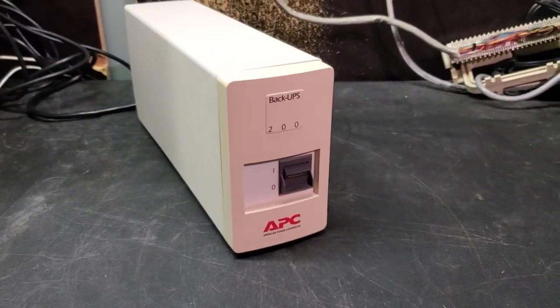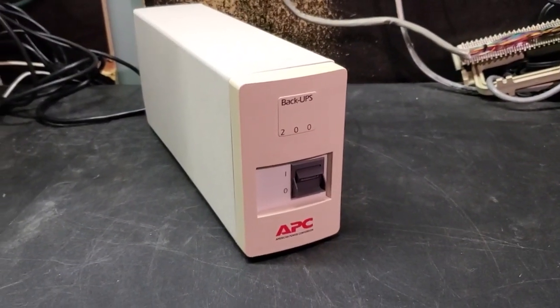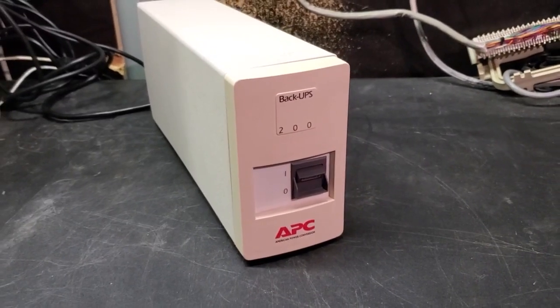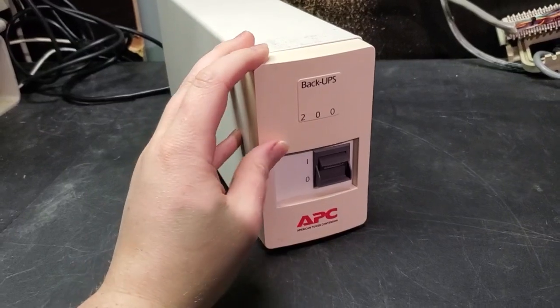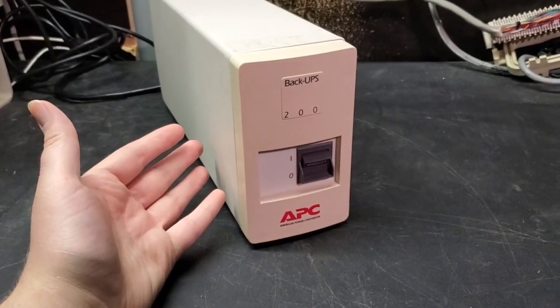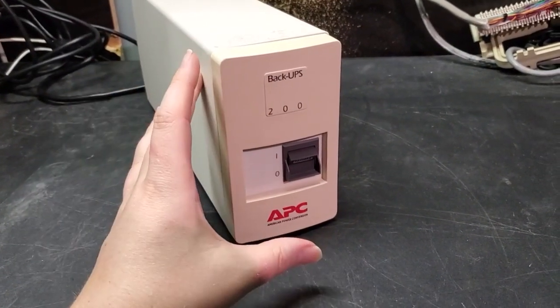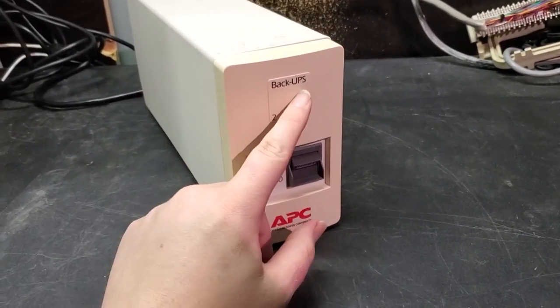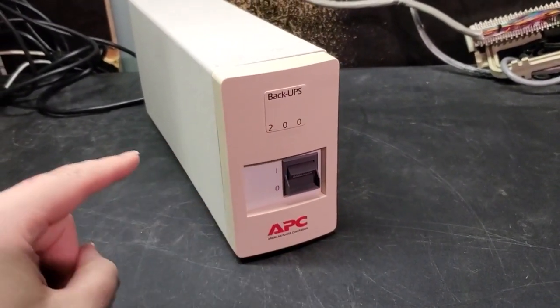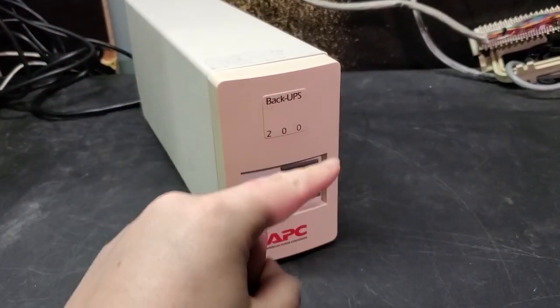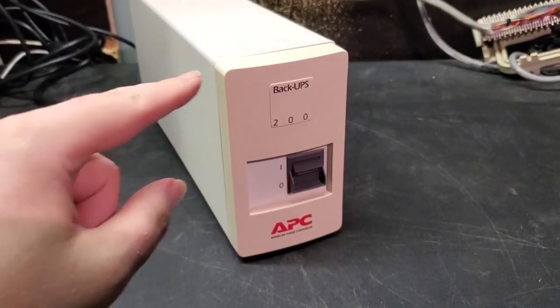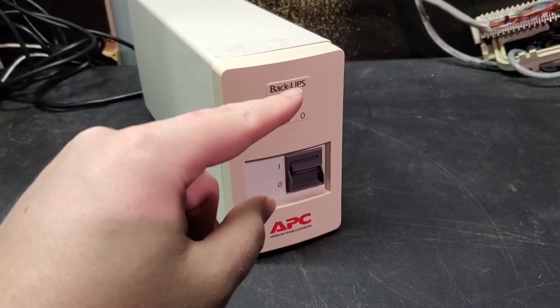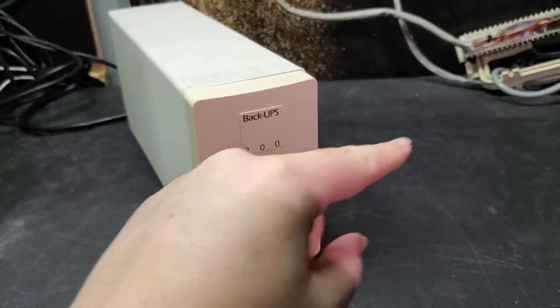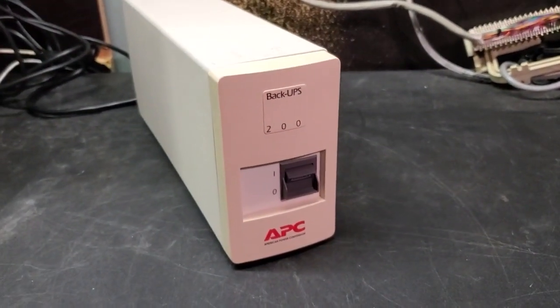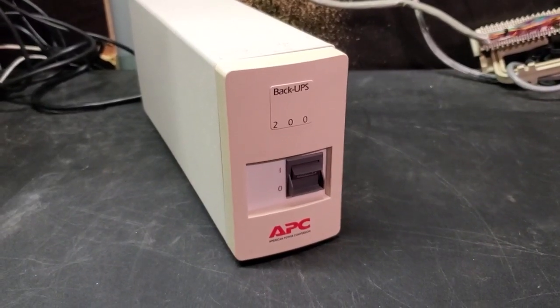Now, one of the implications of this is that these UPSs, especially the back UPSs—the biggest difference between a back UPS and a smart UPS is that the smart UPSs are pure sine wave, while the back UPSs are modified sine wave. The output waveform is basically a stepped square wave: it steps up halfway to the voltage level, steps up again, then goes back down. So it's a stepped square wave output.